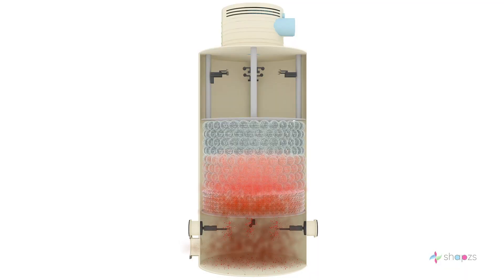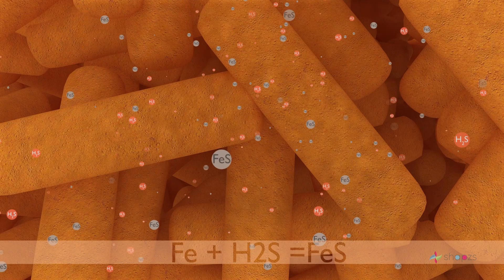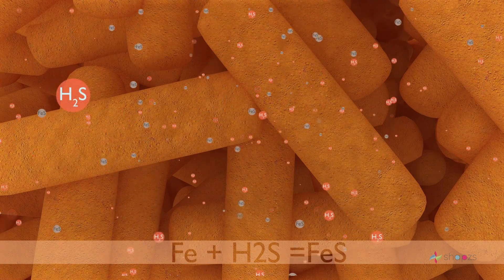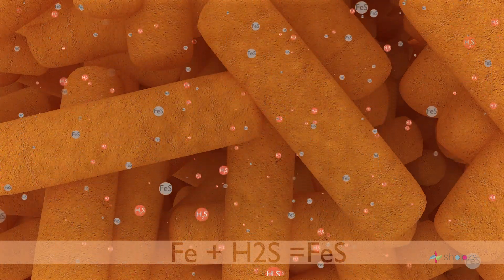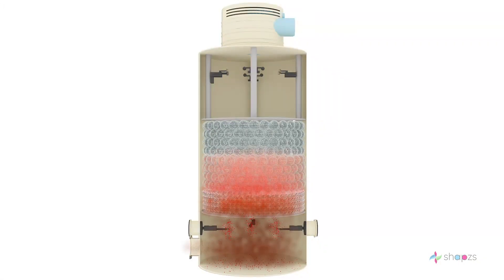This layer has cage balls with ferrous catalyst. The ferrous catalyst will be in yellow color in pellet shape. In this layer the H2S content in the air reacts with ferrous content and is eliminated from air. The height of this layer will be about 500 mm.